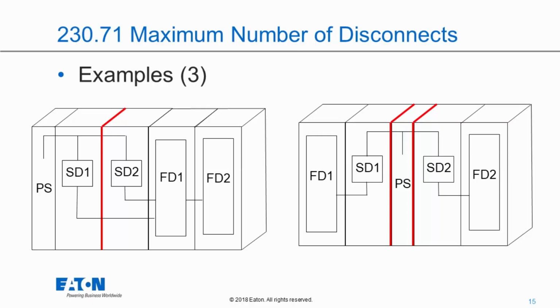If we look at examples of separate vertical structures, I have two different examples here. Here we have a pull section, and we have service disconnect 1 and service disconnect 2, and they would need to be separated by a barrier. The real question is how is that barrier? Is it full height? Is it only where it's separated between SD1 and SD2, so maybe it would only be half the structure? Possibly. There's really no guidance on that. That's where the confusion would come in, and I would highly recommend consulting with your manufacturers on how they do their barriers. And again, the idea is to prevent, if I was to work on the load side of service disconnect number 2, I don't want that arc propagating into service disconnect 1.